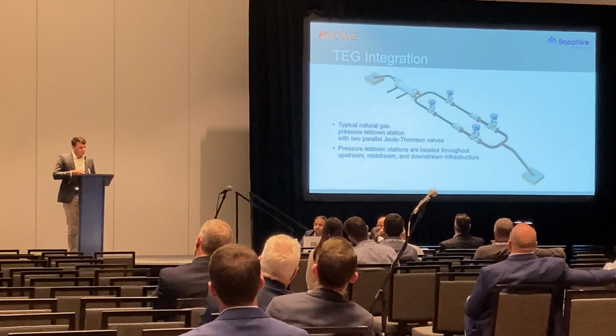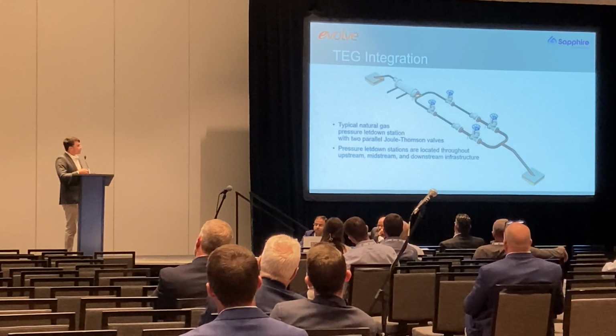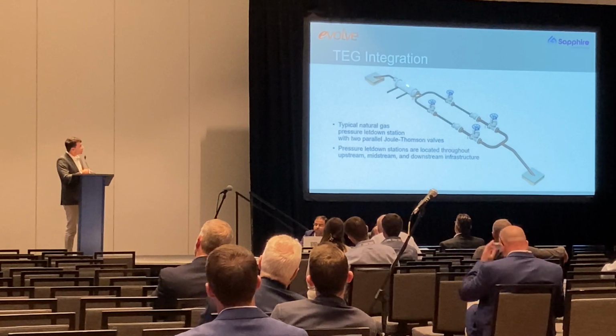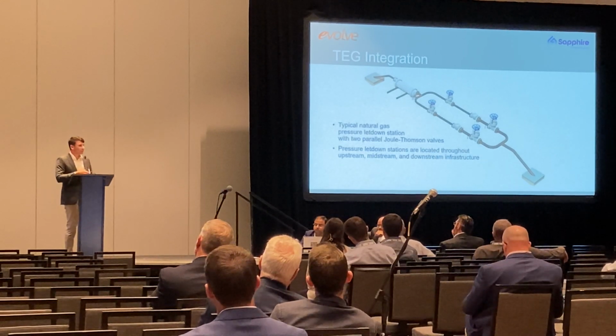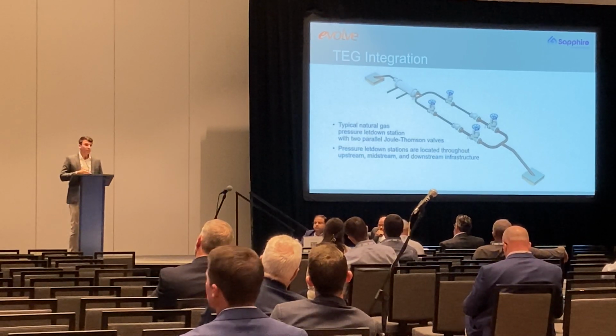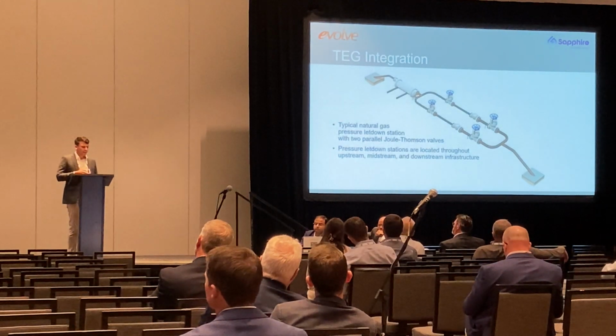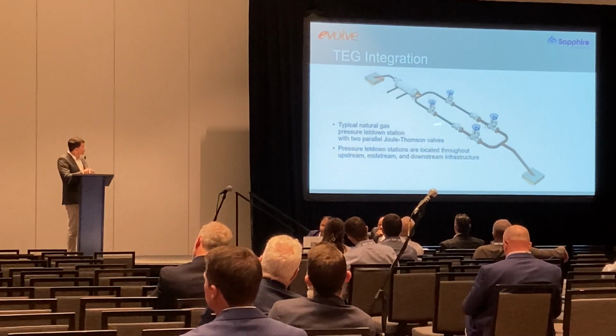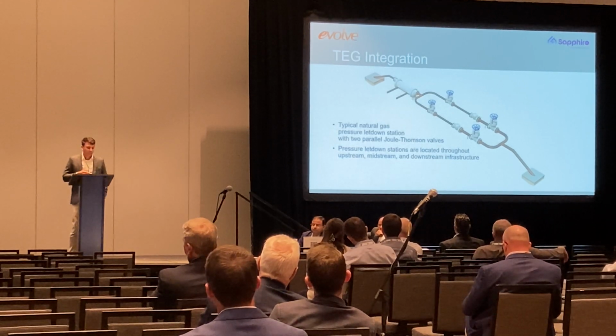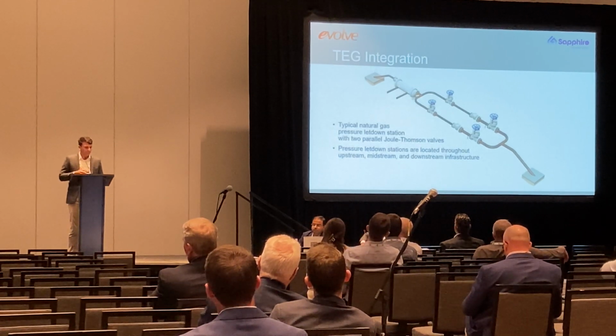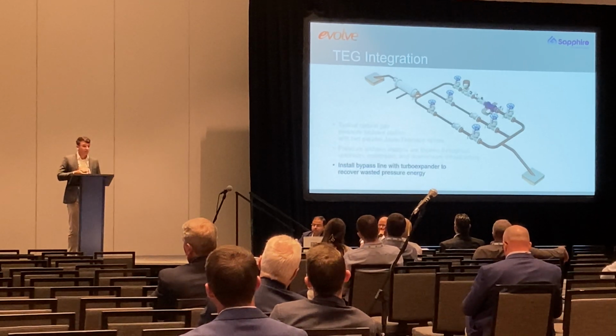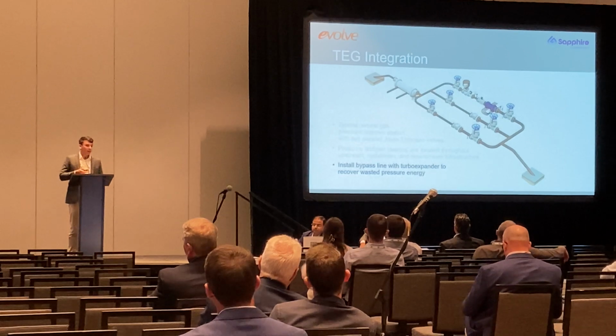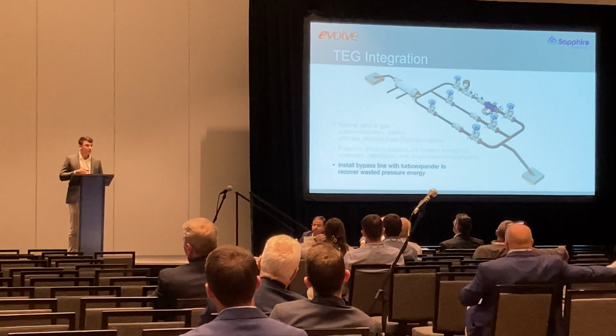An existing pressure letdown station may look something like this. A heat exchanger may be integrated upstream of the regulating valves in order to preheat the gas before expansion. Here you see a couple of Joule-Thomson pressure regulating valves in parallel to each other. A turbo expander can be integrated in or on a bypass line to these existing Joule-Thomson valves.